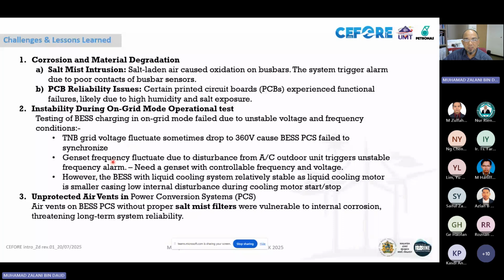Similarly with the genset, we ordered some gensets from a nearby provider in Terengganu. Then we found that to charge the battery, we need a genset with controllable frequency and voltage, because when we use a genset which is not stable in terms of voltage and frequency, it will cause the battery energy storage PCS to be unable to synchronize and trigger some alarms. So these are the two things that we found during our initial start operation: when the grid voltage is unstable, the synchronization of the battery energy storage PCS will not be done properly.